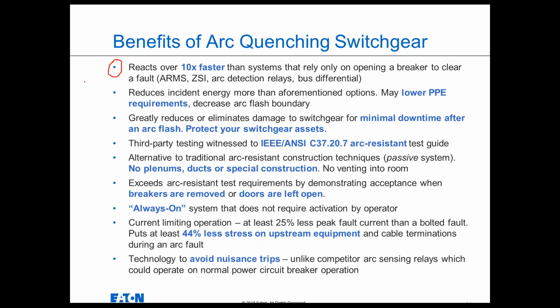First, it minimizes downtime, because if you've got less equipment that needs repairs, or if there's no repairs needed after an arc flash, you're down for a much shorter period of time. But it also just protects what may be a $250,000 piece of switchgear or a $500,000 piece of switchgear. So it saves money by protecting that equipment itself from damage, and obviously it minimizes the downtime of whatever processes are being fed by that switchgear.